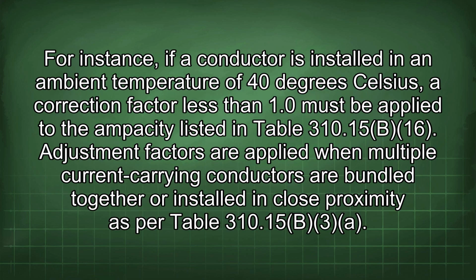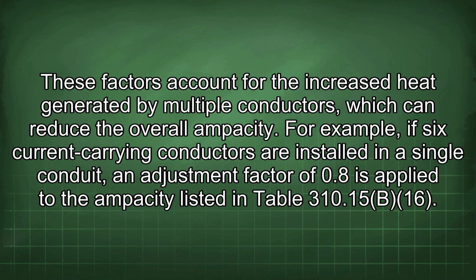For instance, if a conductor is installed in an ambient temperature of 40 degrees Celsius, a correction factor less than 1.0 must be applied to the ampacity listed in Table 310.15(B)(16). Adjustment factors are applied when multiple current-carrying conductors are bundled together or installed in close proximity as per Table 310.15(B)(3). These factors account for the increased heat generated by multiple conductors, which can reduce the overall ampacity. For example, if 6 current-carrying conductors are installed in a single conduit, an adjustment factor of 0.8 is applied to the ampacity listed in Table 310.15(B)(16).